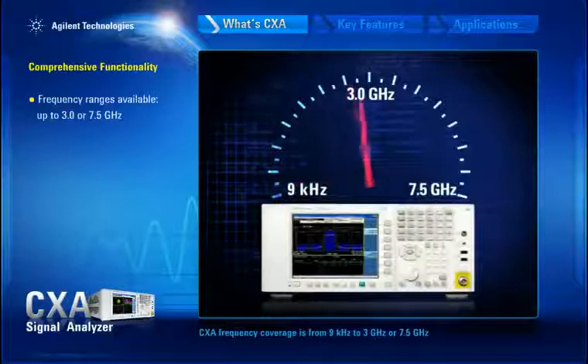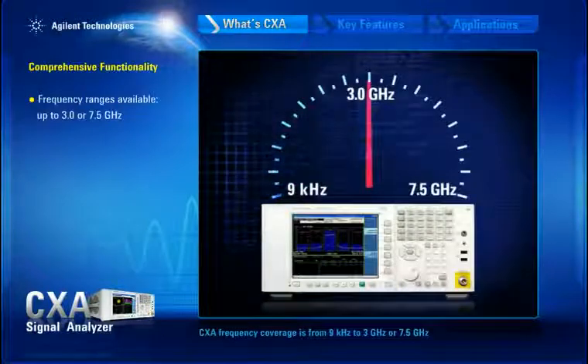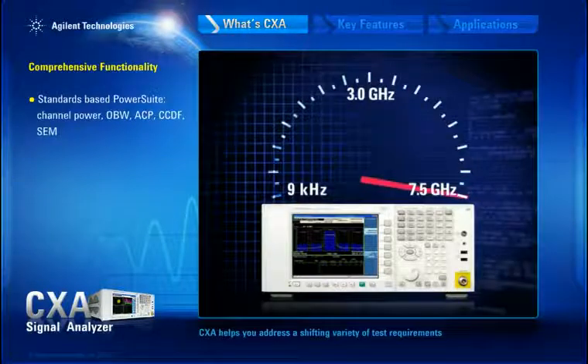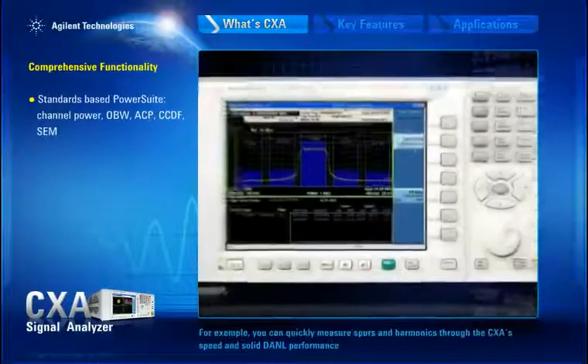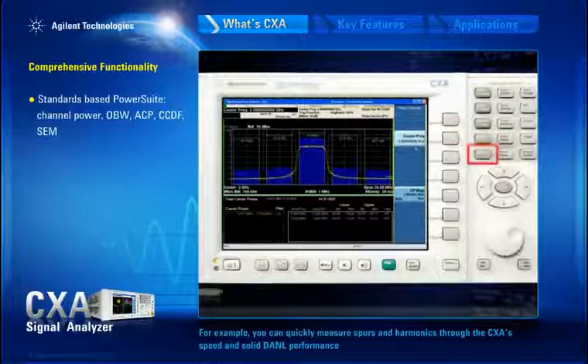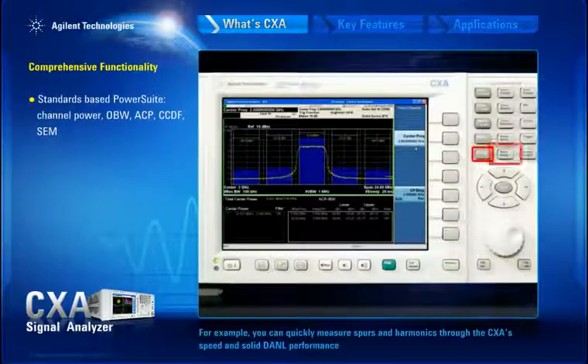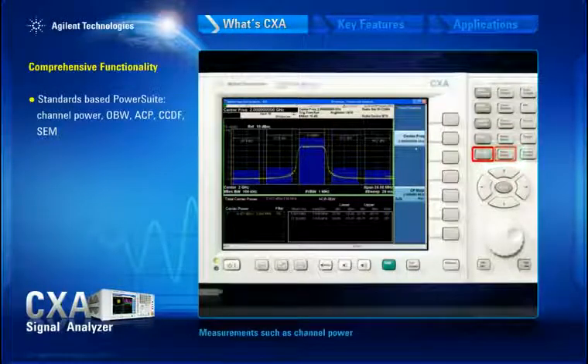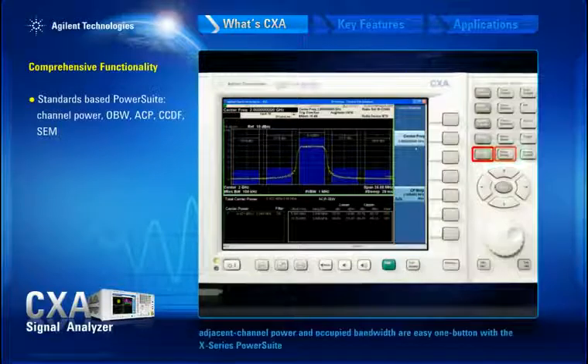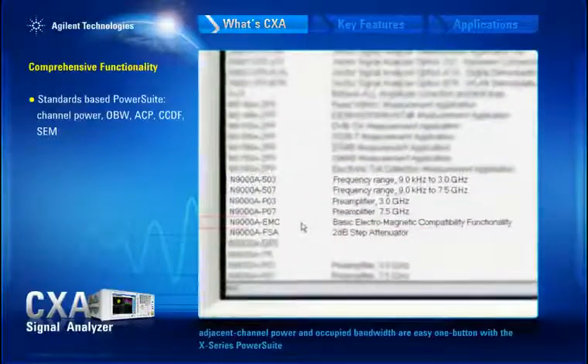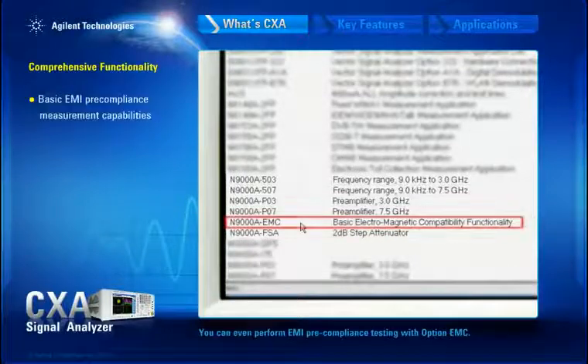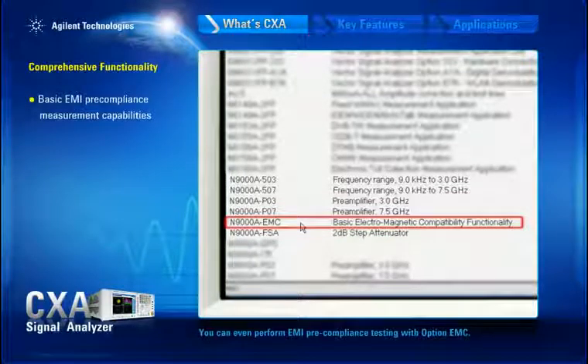CXA frequency coverage is from 9 kHz to 3 GHz, or 7.5 GHz. CXA helps you address a shifting variety of test requirements. For example, you can quickly measure spurs and harmonics through the CXA's speed and solid DANL performance. Measurements such as channel power, adjacent channel power, and occupied bandwidth are easy one-button measurements with the X-Series power suite. You can even perform EMI pre-compliance testing with option EMC.